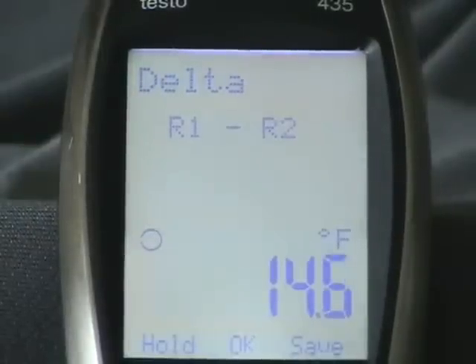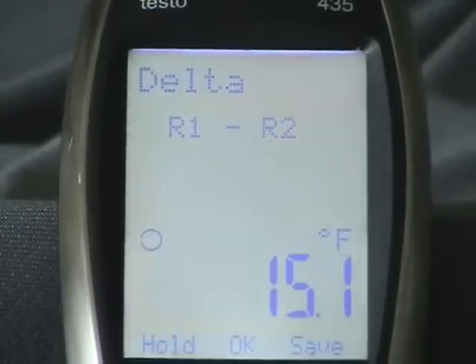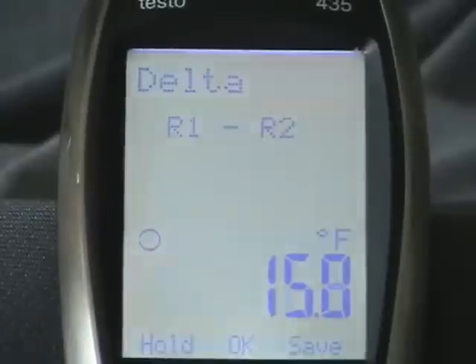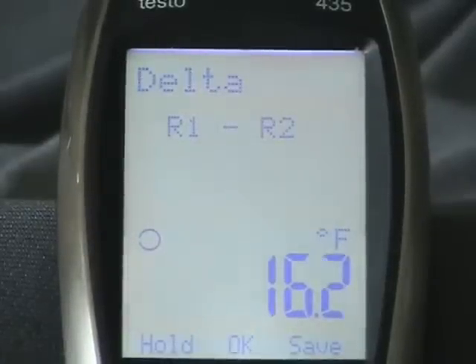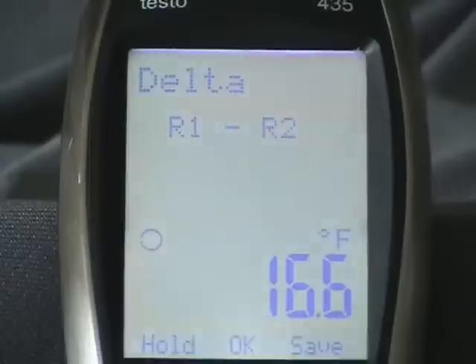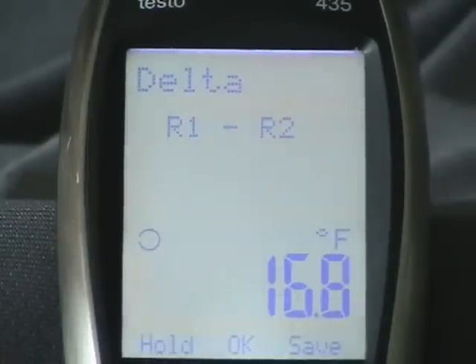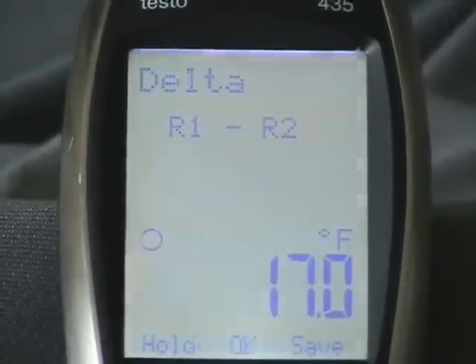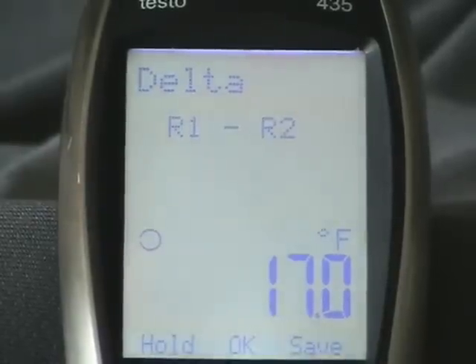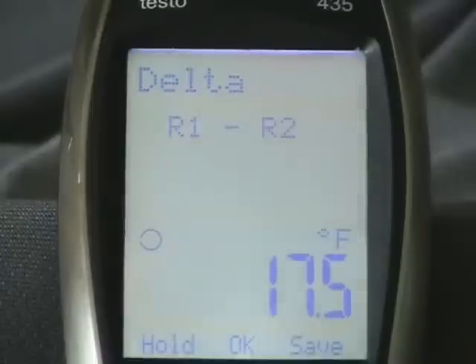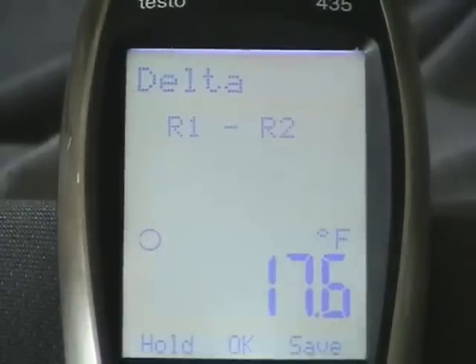Right now I have a 14.6 degree wet bulb split. And before you all freak out and tell me my system ain't working — that's by design. I have a controller in there that modulates the motor speed to remove humidity from the air. Right now we're outside, relative humidity is about 78% today, and inside the house we're running right at 44, 45%. Normally you would see a 9 degree split — you want to see an 8.5 to a 9.5 degree wet bulb split. But that's how you look at the 435 — we'll show you delta on a system real quick, real easy.